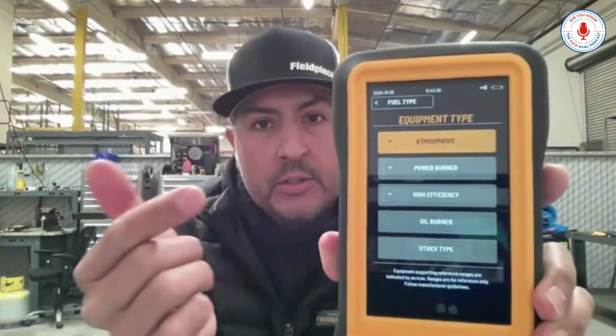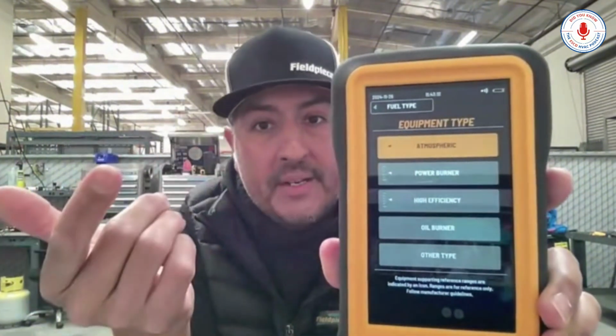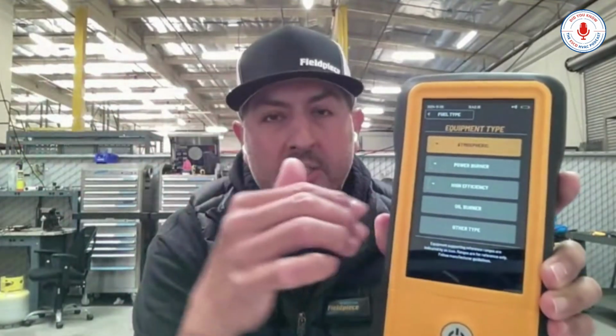Now, once you select the fuel type, you pick the equipment type. Okay. So atmospheric is about a 70% natural draft, right? Power burner is about an 80%, and high efficiency is 90% or above. So I'm just going to go ahead and press on the high efficiency. And now the combustion analyzer is set to high efficiency.